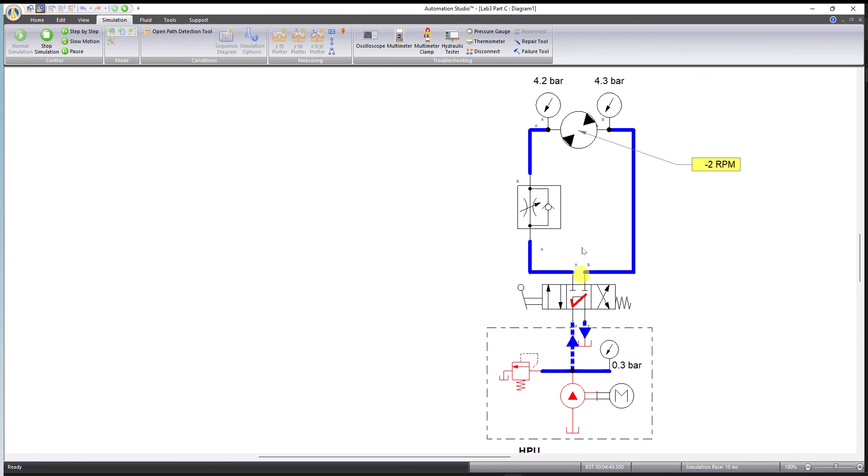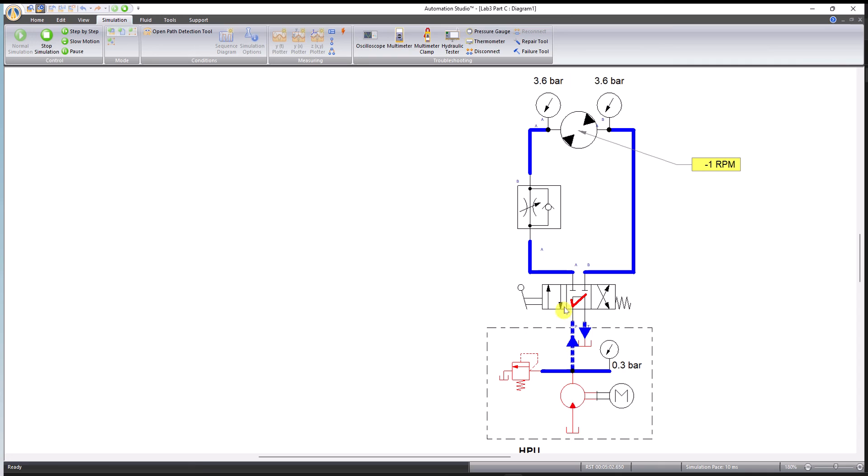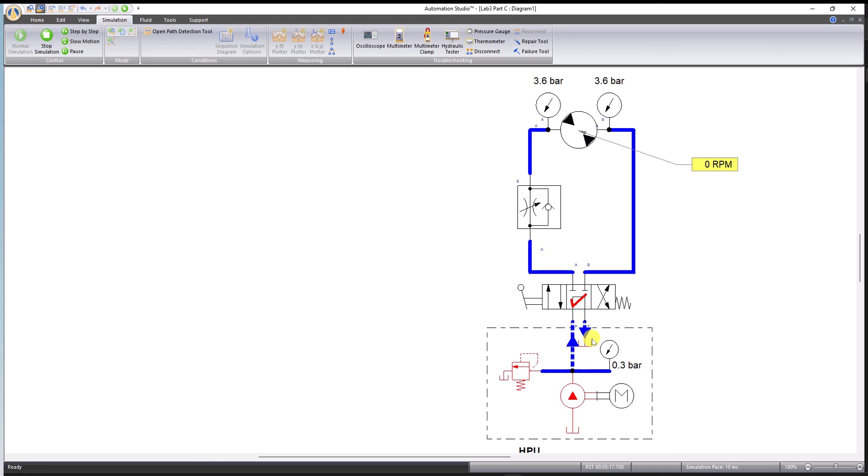Hopefully this was easy to understand. Also pay attention: when we stop the motor from running, right now it's almost stopped, the pump is still running but at a very low pressure. And that's what I mentioned in the beginning: we choose a DCV that will allow the pump to relax or run at low pressure when the motor is not using the flow. So now the motor is isolated from the pump, and the pump is still running but not at high pressure. It is continuously running at blue color, that means at atmospheric pressure, which is great.